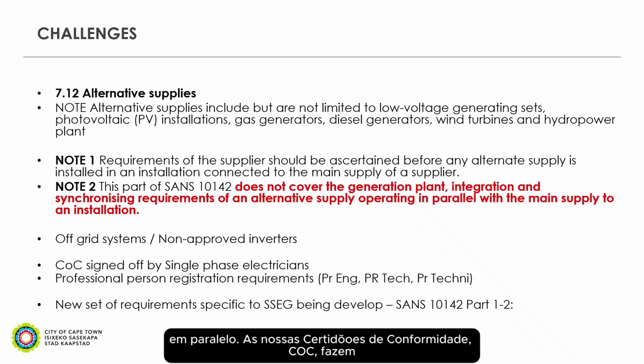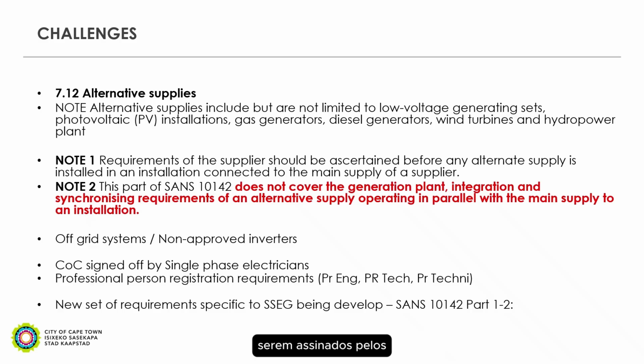Then our COCs, as part of the SANS document, are a requirement to be signed off by the electricians as part of the installation for work being done in the distribution board. And the single phase electricians, unfortunately, in terms of the electrical installation regulations, don't have the necessary DC installation experience, and therefore we do not allow them to sign off these SSEG installations. We actually require professionally registered persons with ECSA to sign off these systems together with the COC from the installation electrician or master electrician, but not the single phase tester electrician.